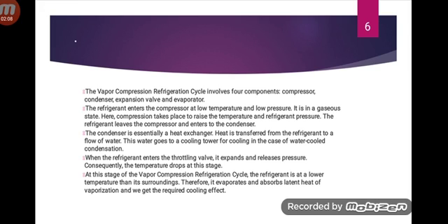Here the compression takes place to raise the temperature and pressure of the refrigerant. The refrigerant leaves the compressor and enters the condenser. The condenser is essentially a heat exchanger. Heat is transferred from the refrigerant to the flow of water. This water goes to a cooling tower for cooling in the case of water-cooled condensation.